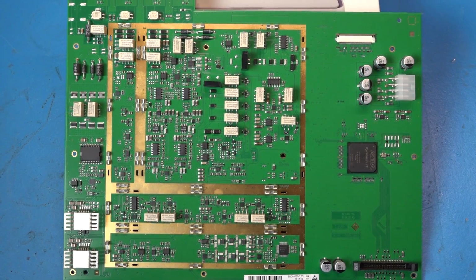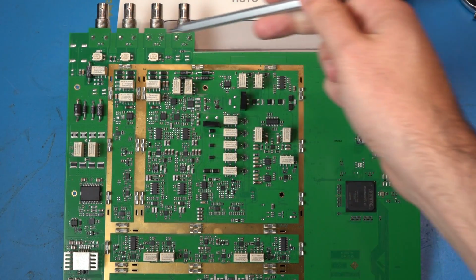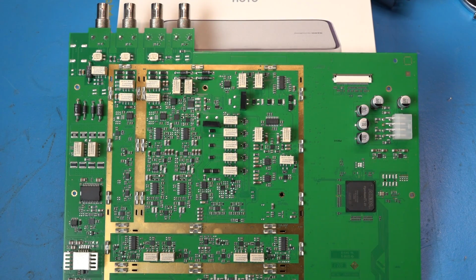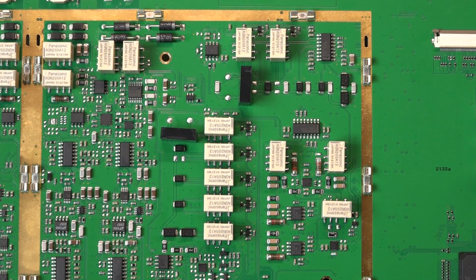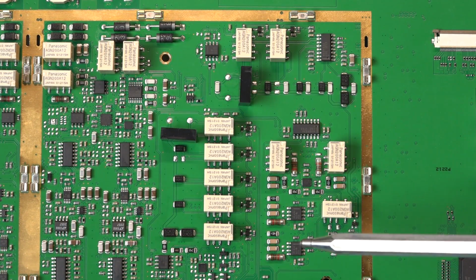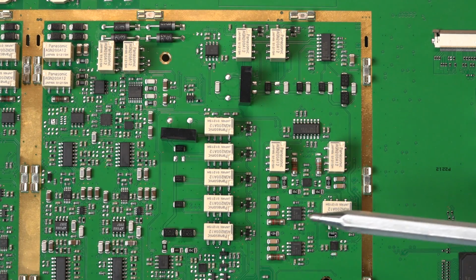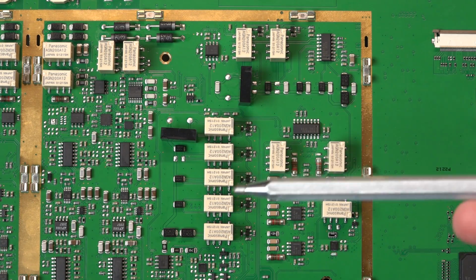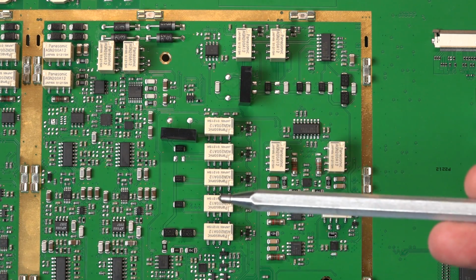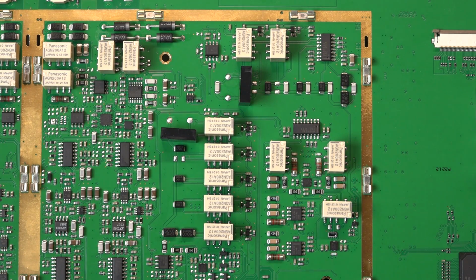If I go up a little bit higher, the connectors are directly mounted to the board, minimizing all the interface inductances and capacitances and all the interactions they may have with each other. And these are our genuine Panasonic switches. They're pretty important to be of high quality because they switch a lot depending on how the auto ranging is set inside the instrument and how many different values of measurements are being done in a row. So it's good to see that high quality components are used throughout the unit.